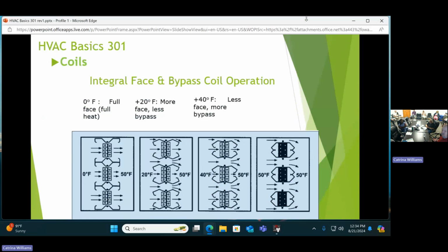As outside air warms up to 40 degrees, you're almost totally closed off on the fin tubes, getting a little bit of air through there, and most of it's going through the bypass because you've only got to make up for 10 degrees to get to 50 degrees. And then as you get to 50 degrees, the fin tube dampers are totally closed off and you're just strictly bypassing air.